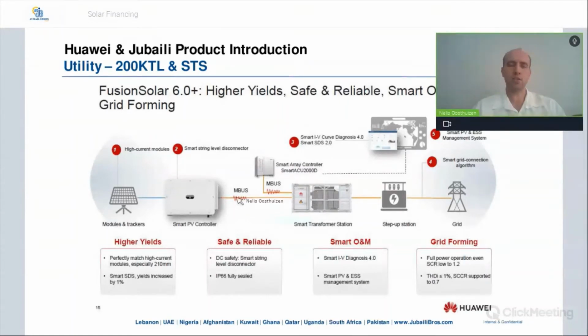A nice feature of the Huawei inverters is M-bus communication, which means you don't need to run separate RS485 cables to each inverter or transformer station. Communication can go via the power cables with M-bus, saving on capex for cables and digging extra trenches to separate power and communication cables. So there's a big saving there.